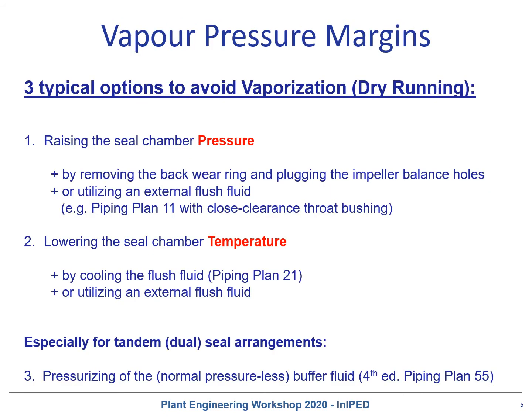How can the required pressure margin be maintained? There are three options to suppress or avoid dry running. First, raising the seal chamber pressure by removing the back wear ring, or plugging the impeller balance holes, or utilizing an external flush fluid in combination with a closed clearance throat bushing — utilizing a Plan 11 from the discharge nozzle, from the higher pressure source.